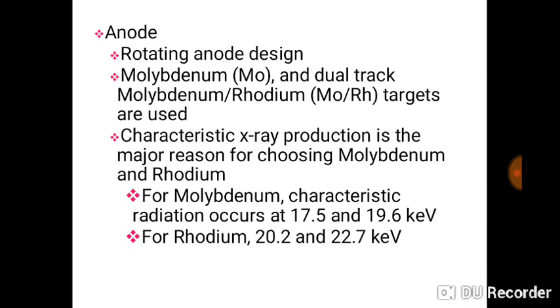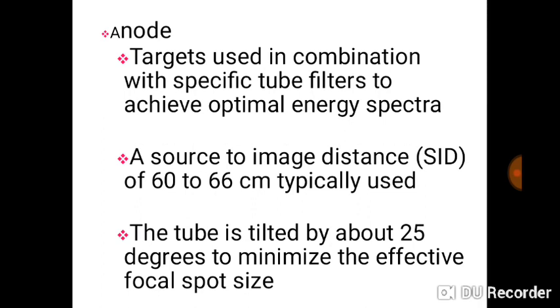The anode is rotating and uses molybdenum, with a dual track which could be molybdenum and rhodium targets. Characteristic radiation is the major reason for choosing these metals. The targets are used in combination with specific tube filters to achieve optimal energy.